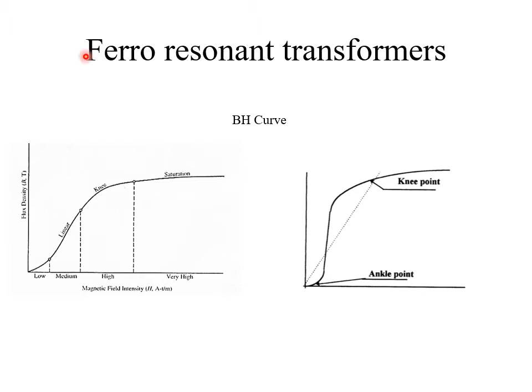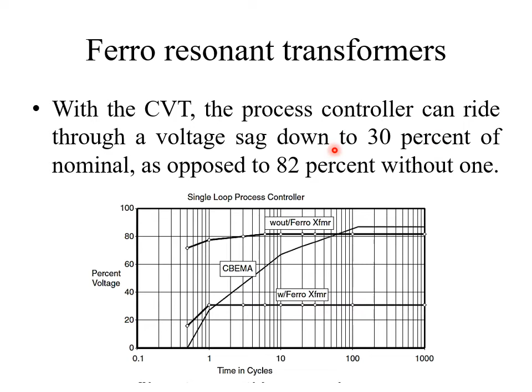Here you can see the CBEMA curve, and you can see two bold lines. One is without the ferro-resonant transformer and another one is with the ferro-resonant transformer. So what is the inference? This is the percentage voltage magnitude. Under normal condition, the equipment will operate in the range of 90 to 110 percentage. But with the ferro-resonant transformer, even though the voltage reduces to 30 percentage, it can still operate, because the ferro-resonant transformer enables the equipment to operate in this safe region. That is why it is mentioned that a voltage sag down to 30 percentage can also be operated with a ferro-resonant transformer.